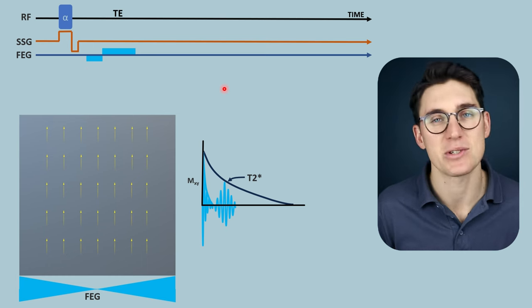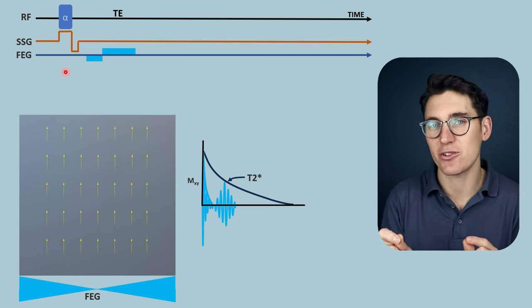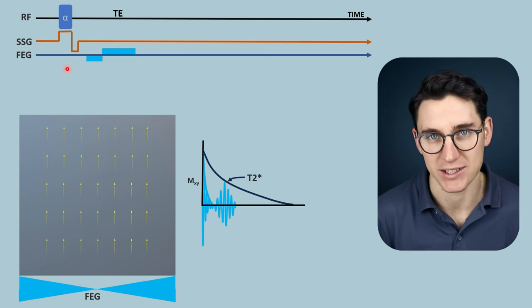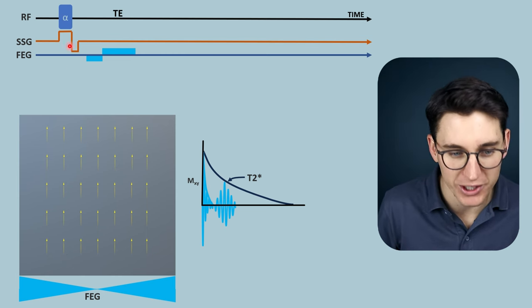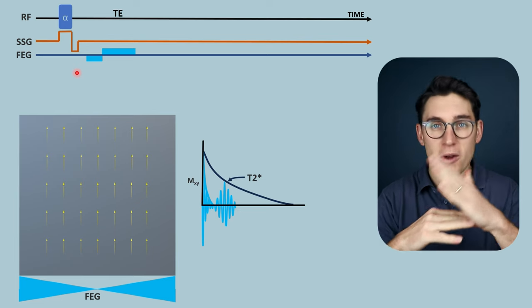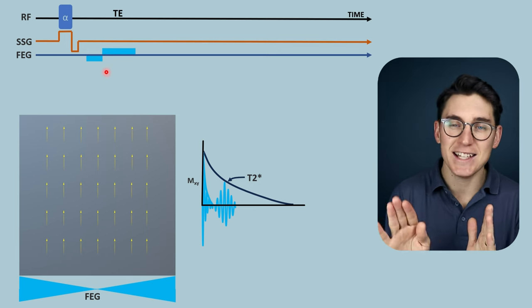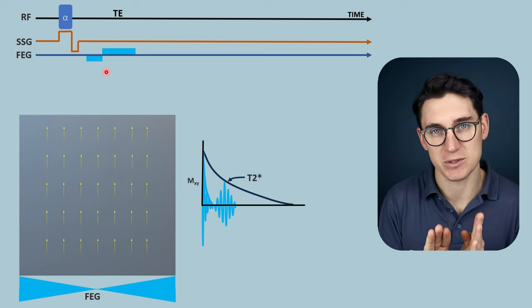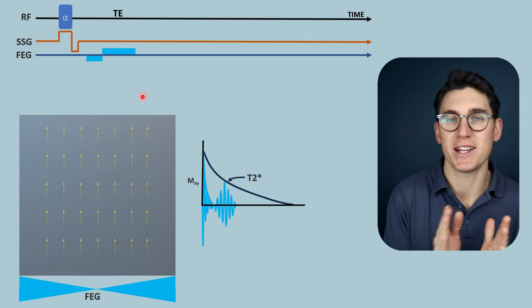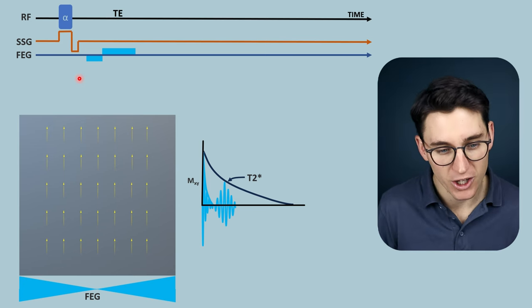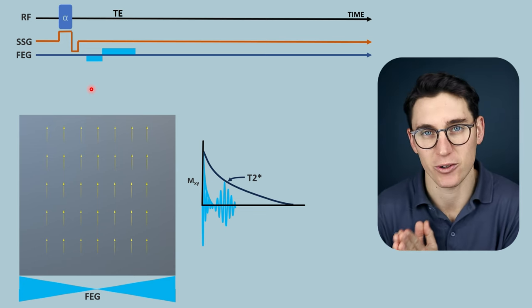In a gradient echo sequence we only require one radio frequency pulse — we don't need that second RF pulse that generates the echo in spin echo imaging. Having only one RF pulse, and often using a pulse that doesn't flip spins 90 degrees but uses smaller angles, also allows us to bring the TE much closer to that single RF pulse. Since we're reading T2 star and signal is lost rapidly, we need to bring the TE close to the RF, making this initial part of the sequence much faster than in spin echo imaging.